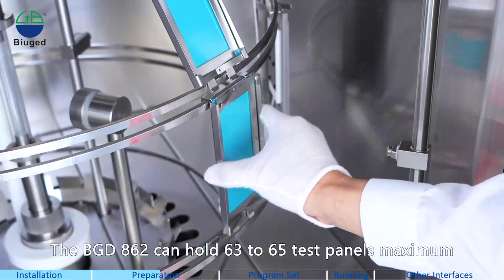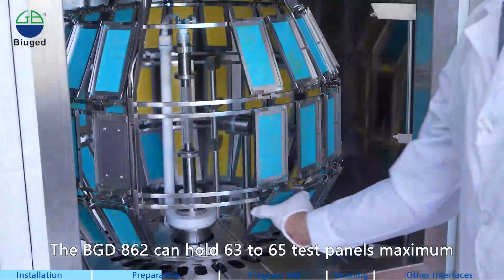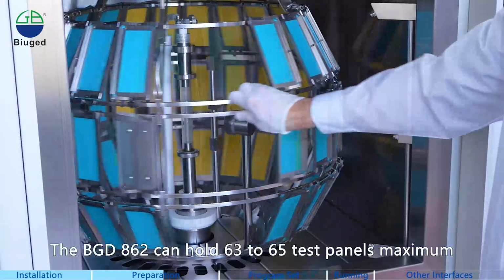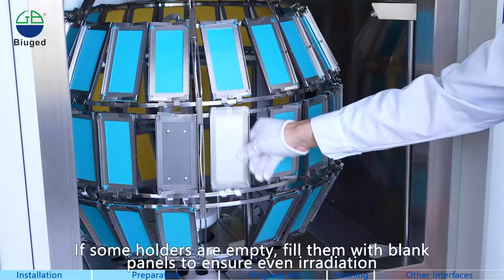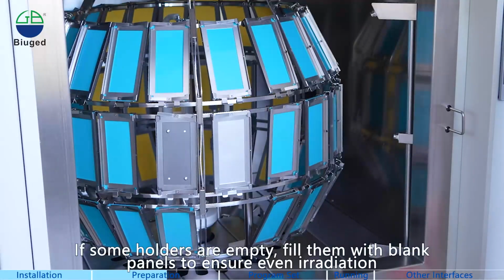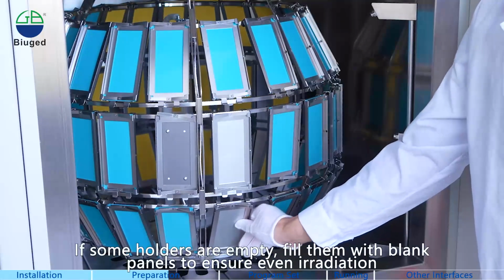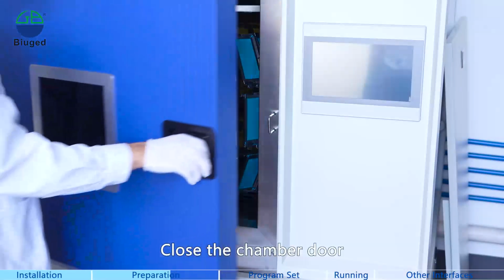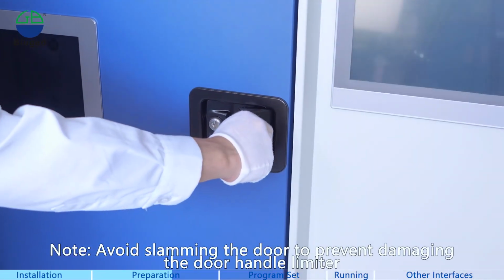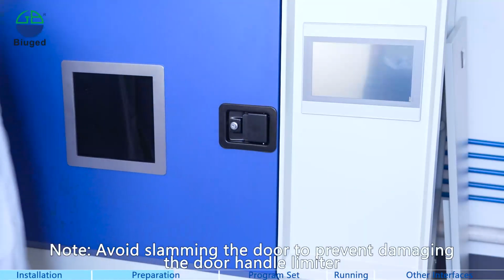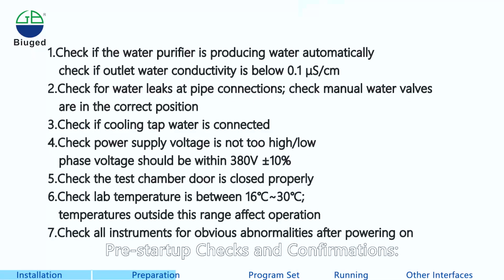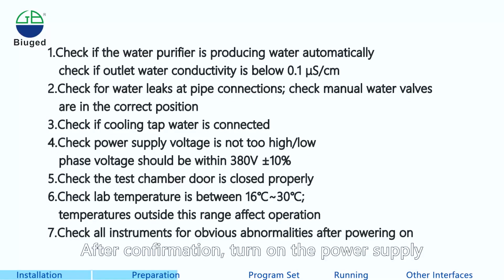The BGD 862 can hold 63 to 65 test panels maximum. If some holders are empty, fill them with blank panels to ensure even irradiation. Close the chamber door. Note: avoid slamming the door to prevent damaging the door handle limiter. Pre-startup checks and confirmations. After confirmation, turn on the power supply.